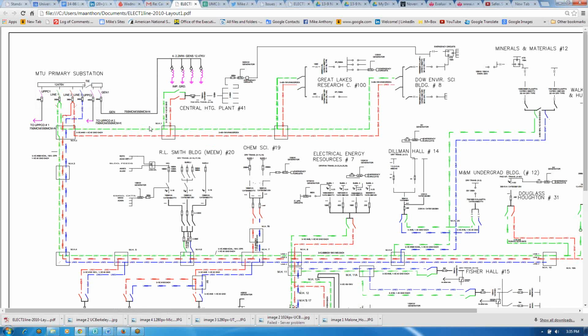But in the building premises wiring system, if you consider that the Michigan Tech system here is a premise wire system, arguably, even though you have many buildings, it's likely that your service starts here. This is where your electrical inspector might say, this is where the service is, and I don't care about anything going on downstream. In other cases, yeah, that's true. So in other cases, that same inspection authority may look at this substation and say, wait, all this is utility wiring, and this is where my focus of inspection is going to be.